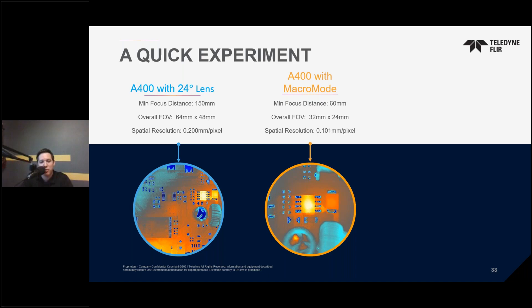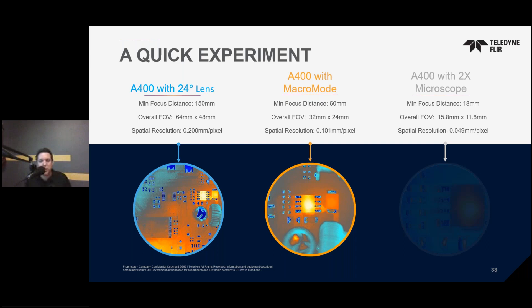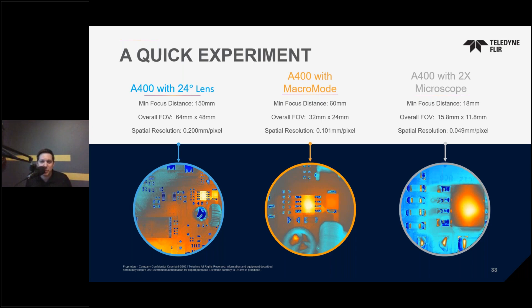But what can we do with a 320 by 240 detector? We can do a little bit better. Let's use the 2x microscope lens. With that lens, the working distance of the camera is just 18 millimeters. The overall field of view shrinks to 15 by 11 millimeters, and you can see the individual components much more clearly, with a new spatial resolution of just 49 micron per pixel — meaning 200 pixels on that one 0402 component, giving you great temperature measurement data and even the ability to see thermal variations across it.